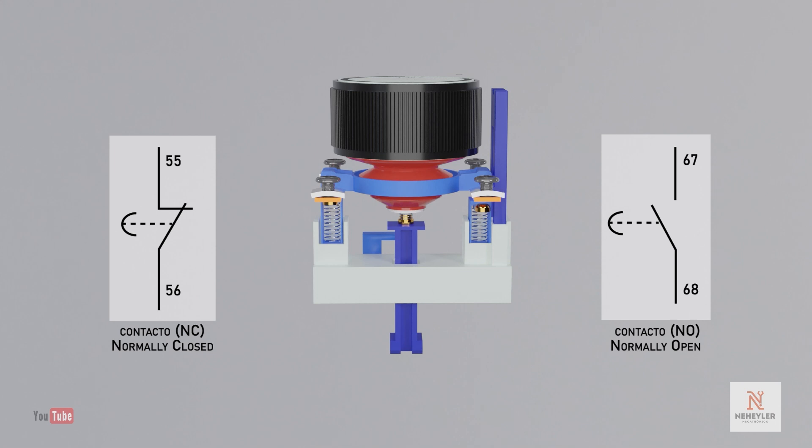When the contactor coil is energized, it then allows the timer latch to be pulled. Therefore, the bellows deforms and travels a certain distance until it activates a small lever, which allows the contacts to change state. That is, contact 55-56 opens and contact 67-68 closes.